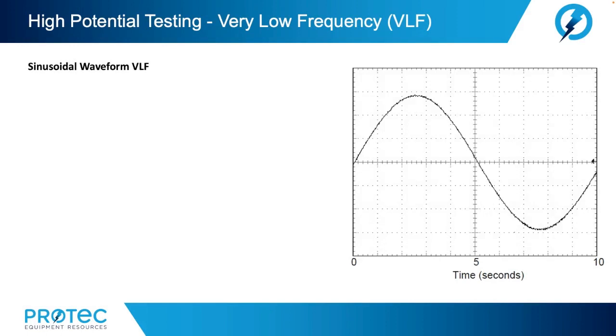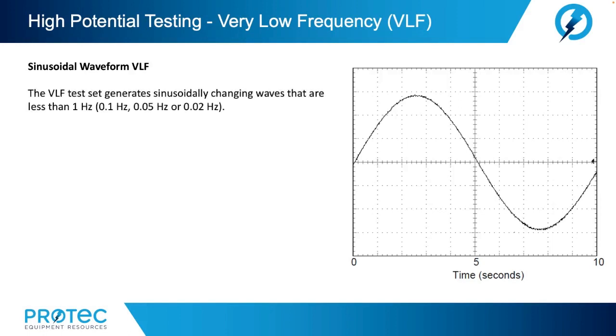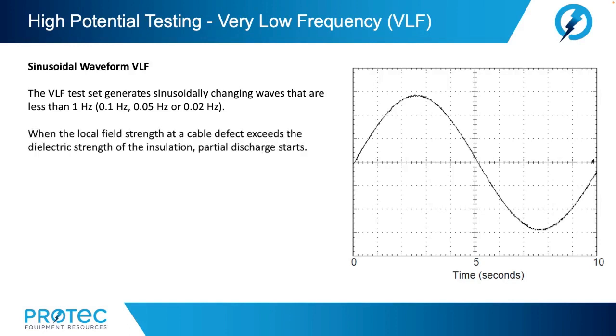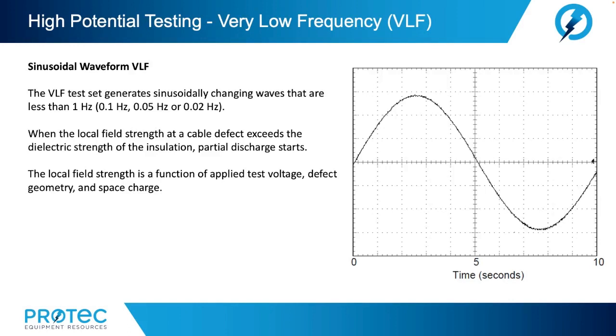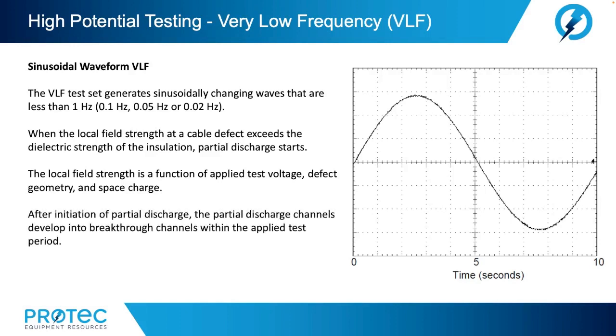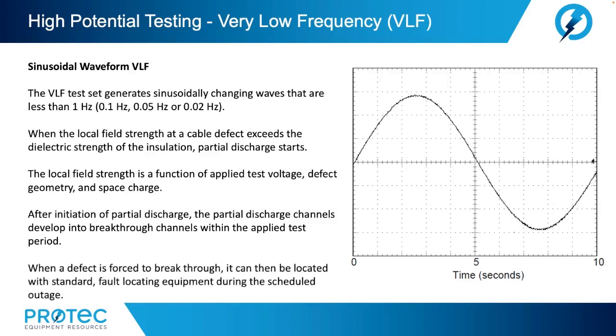Now, let's look at the sinusoidal waveform version of the VLF test set. The VLF test set generates sinusoidally changing waves that are less than 1 hertz, typically 0.1 hertz, 0.05 hertz, and 0.02 hertz. When the local field strength at the cable defect exceeds the dielectric strength of the insulation, partial discharge will occur. The local field strength is a function of the applied voltage, defect geometry, and space charge. After initiation of partial discharge, the partial discharge channels develop into breakthrough channels within the applied test period. When a defect is forced to break through, it can then be located once again utilizing standard fault locating equipment during a scheduled outage.